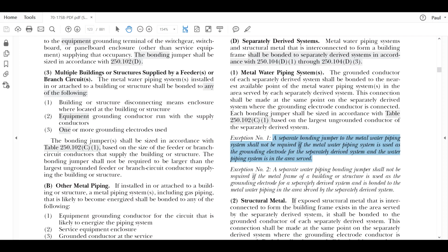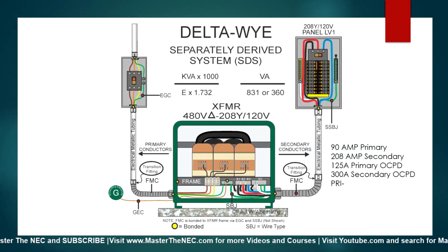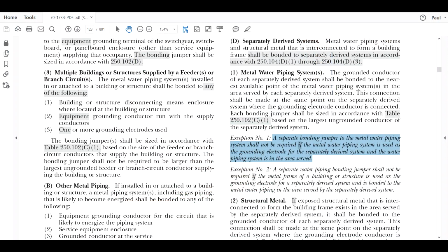So if it's already having this, let's go back and I'll show you. If you already had the requirement for this grounding electrode conductor to go to the water pipe ground, then it's pointless to take another one out to the metal water piping of the system in the building. It would be pointless, right? So that's the exception. It says, all right, you've already done it once, you don't have to do it again. We don't need to do it twice. So that's what that rule means.